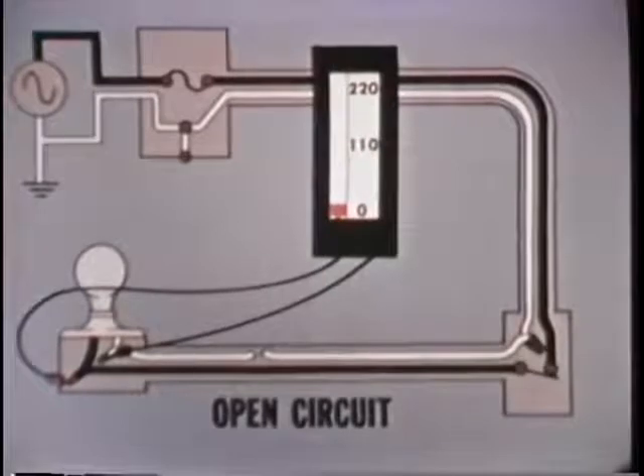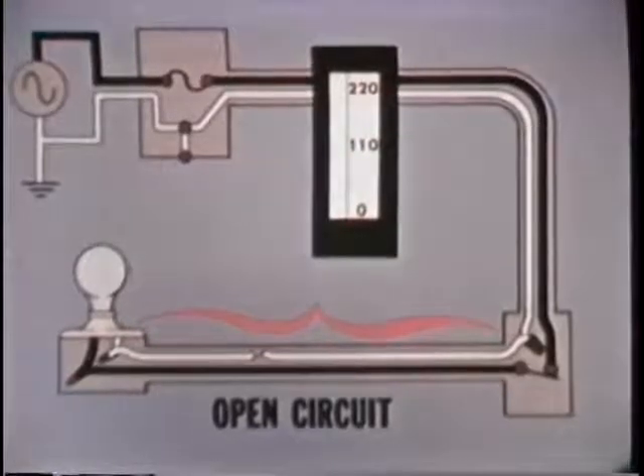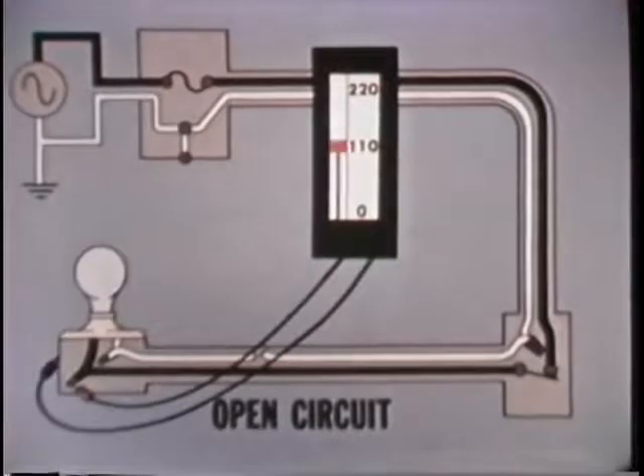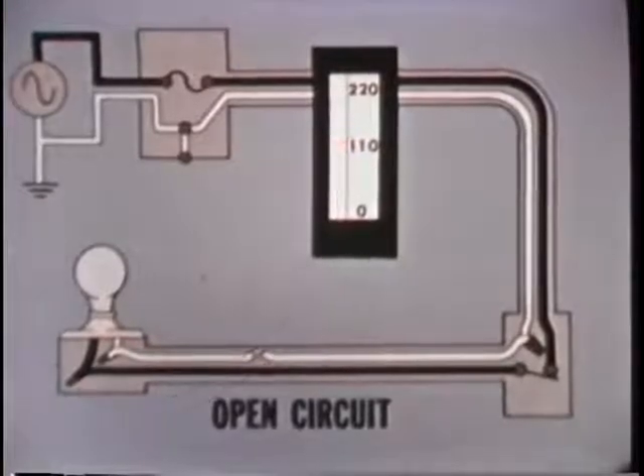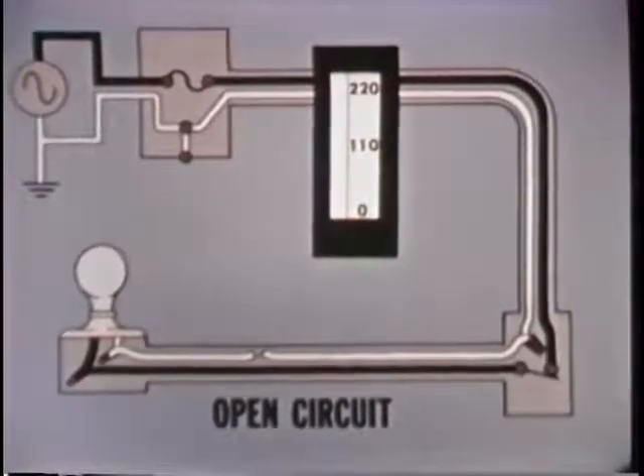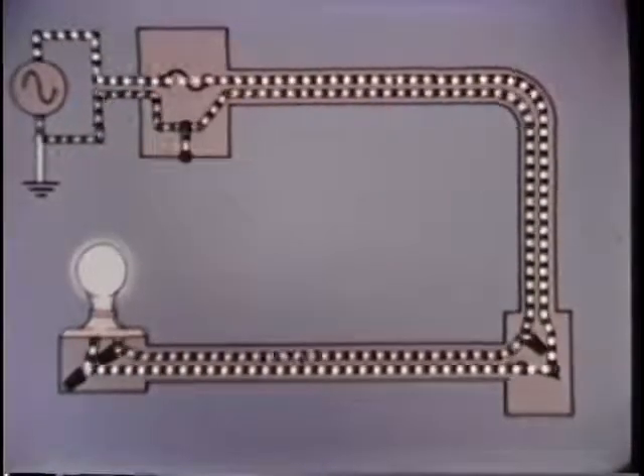The final checkpoint is at the fixture box. At this point, there is no voltage. The trouble has been traced to this section of conduit. However, continuing a step farther can determine which conductor is defective. A check between the hot conductor and ground indicates 110 volts, which proves that the hot conductor is continuous. So, the open circuit must be in the neutral conductor. Replacing the defective section of neutral conductor restores the service.